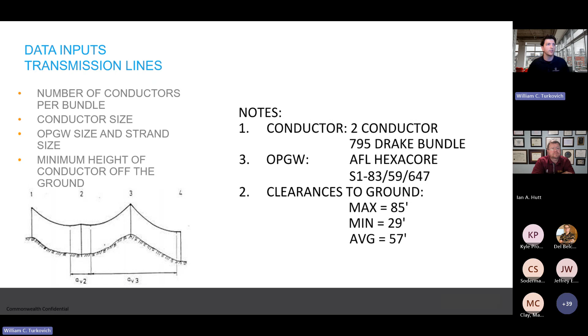Let's say you are running a transmission line - what does the transmission line go to? It goes to a substation, maybe a collector station for a wind farm or solar farm. What do you need for that? We can do an EMF analysis of that. We'll need the conductor sizes, the tubes and how thick they are going from each piece of equipment, the voltage levels of the equipment, the transformer size, the breaker size, the collector buses and breakers.